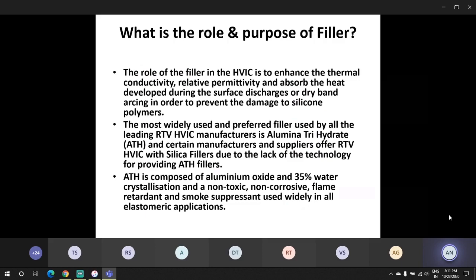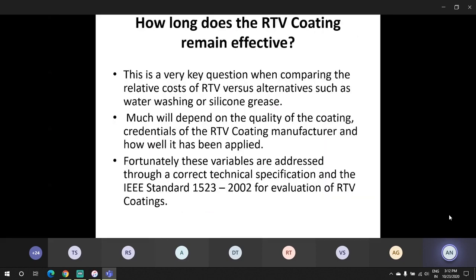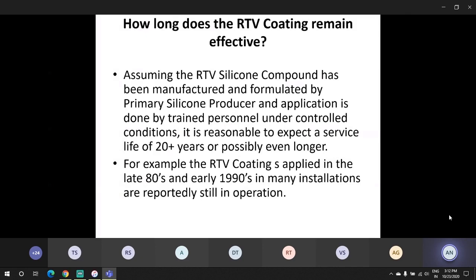This is a filler. Certain manufacturers use ATH, certain manufacturers use silica. And how long the RTV coating remains effective will depend much on the quality credentials of the RTV coating manufacturer and how well it has been applied. The IEEE guide, which has been updated in 2018, can be referred to for any guidance. We can confidently say the service life of the coating will be 20 plus years. In India, our oldest coating is now in service for more than 16 years. And outside India, our coatings which were done in the 1990s are still in operation.